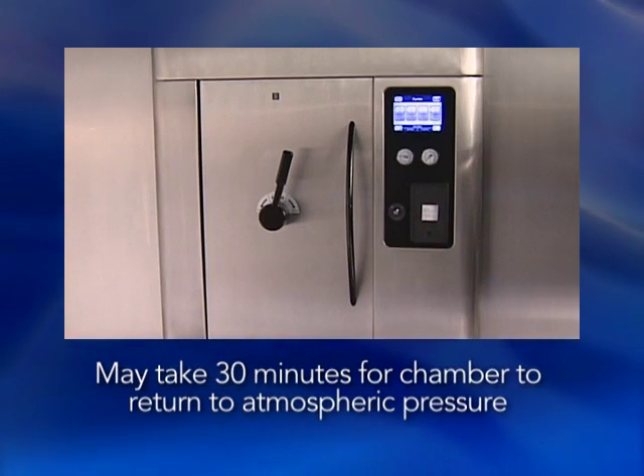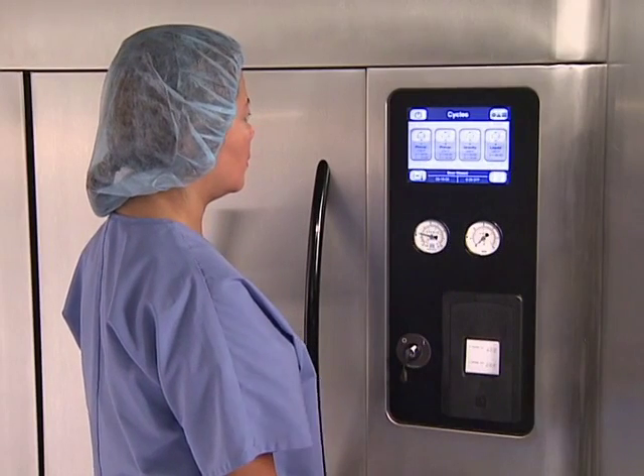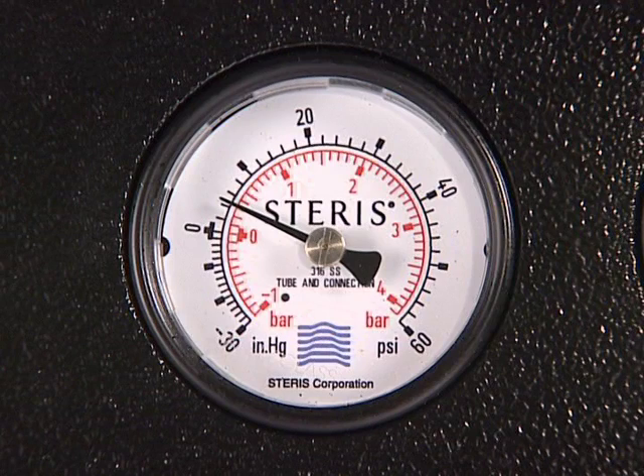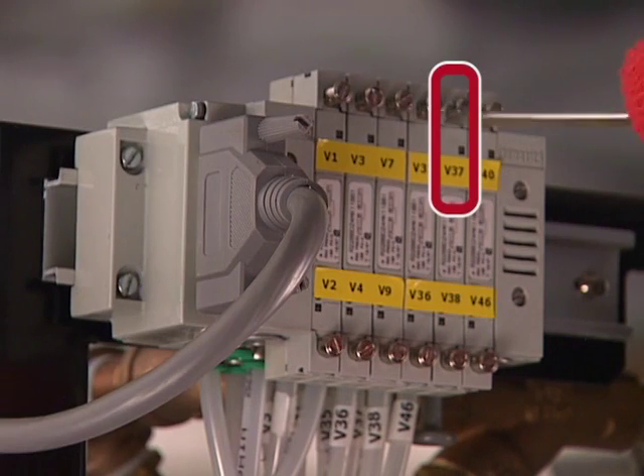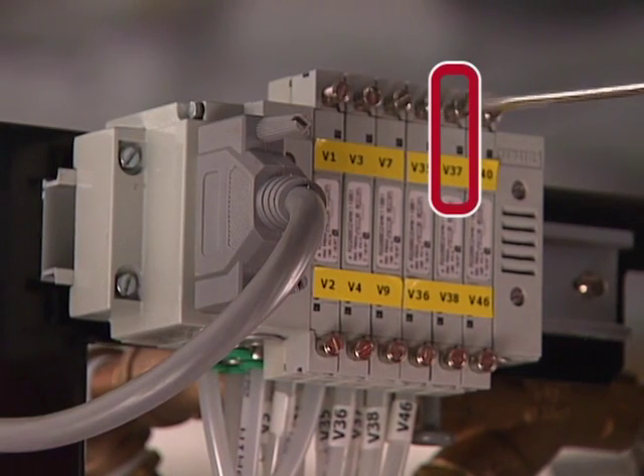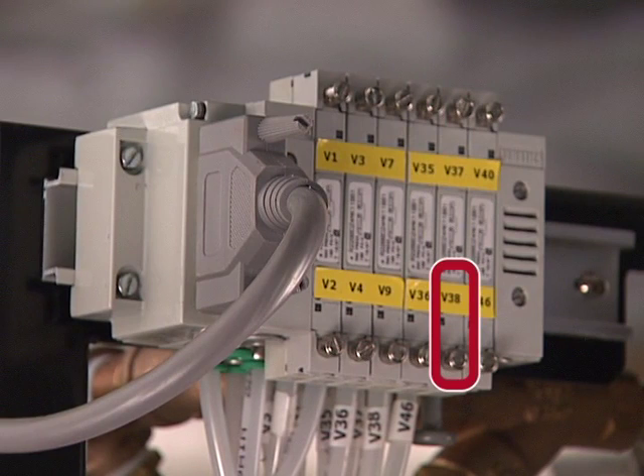This may take up to half an hour. During this time, you'll need to watch the gauge. When the pressure reaches 5-pound force per square inch or the vacuum reaches 5 inches of mercury, open the V37 valve on single-door sterilizers or the V38 valve on double-door sterilizers.